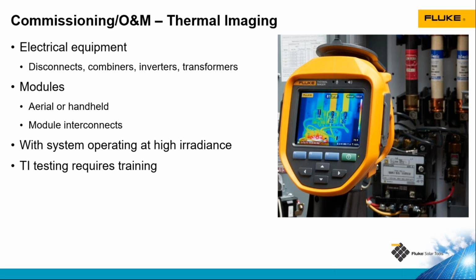Also, thermal imaging is a little different than other tools that we have in the Fluke portfolio. You can't just take a thermal camera out of the box and expect to get good image results. You really need some training to make sure that you know how to take pictures properly and avoid certain issues with thermal imaging. For example, one we run into quite frequently in solar is taking a picture of a solar module and you see a hot spot on it, and it turns out the hot spot is really just the reflection of the sun. And so training will teach you how to avoid issues like that.